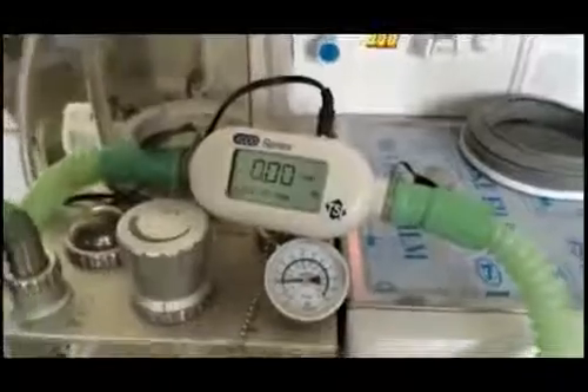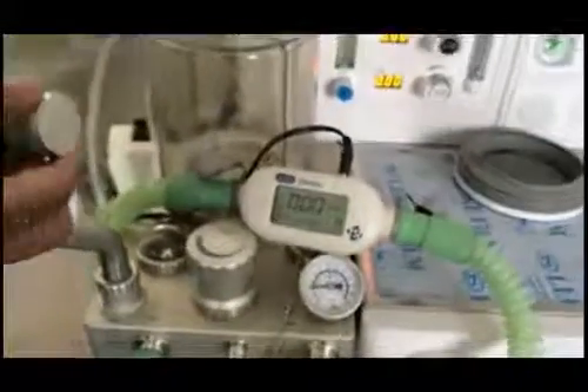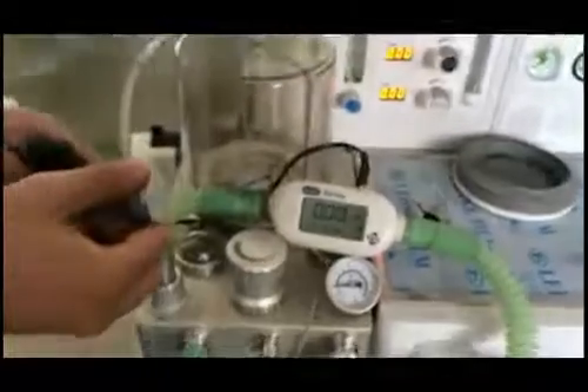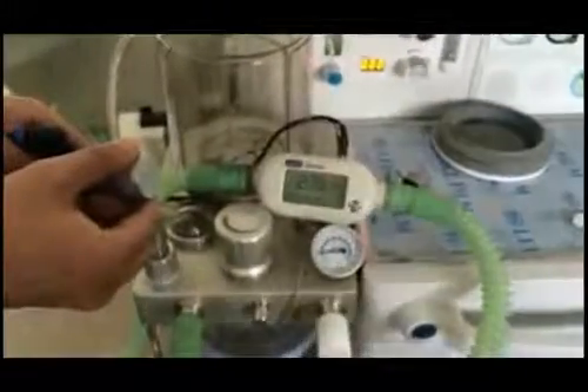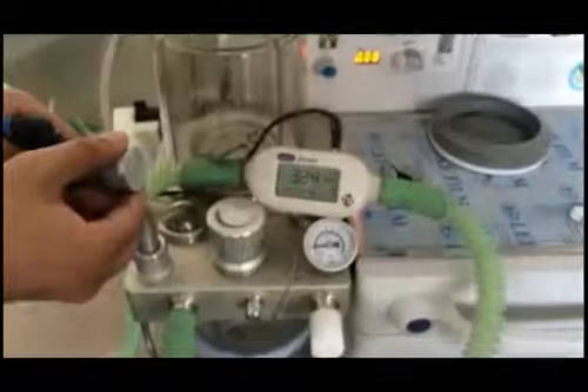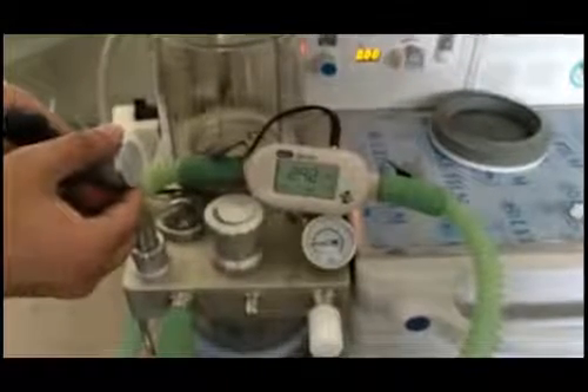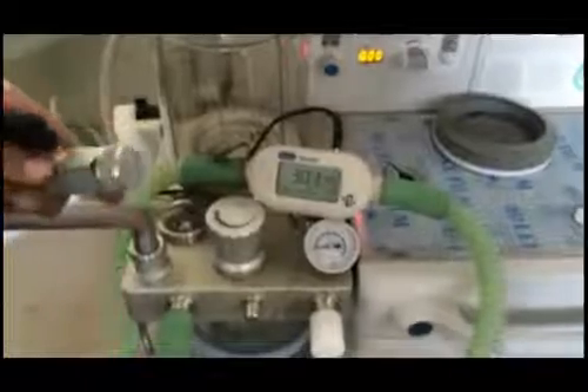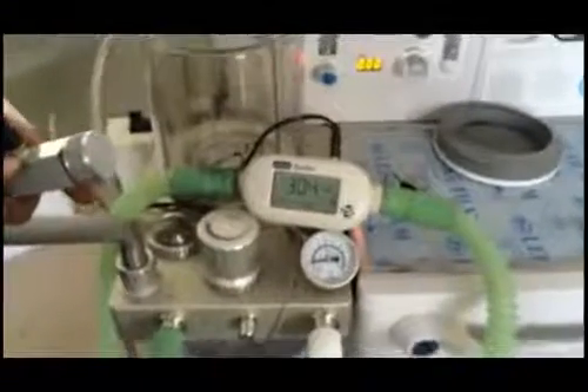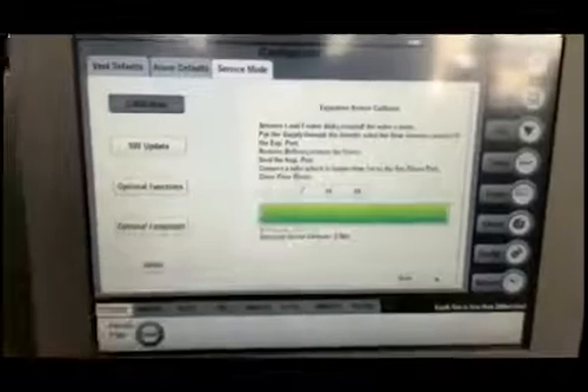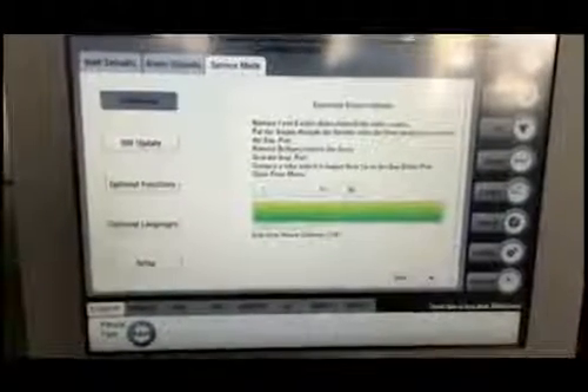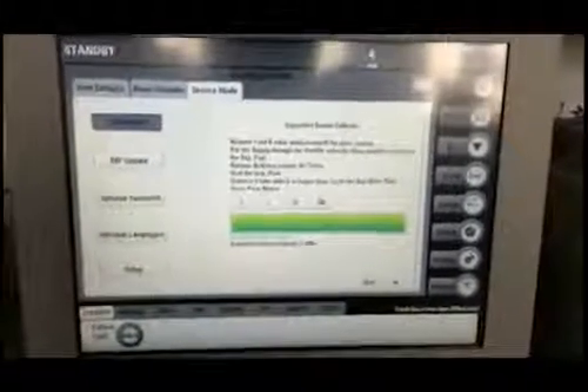Now we will perform the calibration for 3 liter per minute. Please rotate the throttle. Rotate the throttle until the value 3 is reached on the flow meter. After the value has been reached, please press the 3 key on the screen. After the calibration is successful, the calibration successful sign will be displayed on the screen. The next is to perform the calibration for 12 liter per minute.